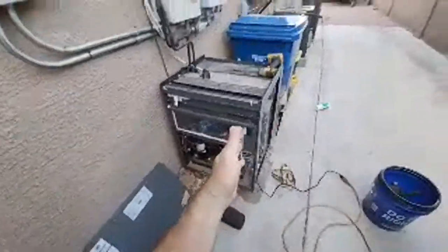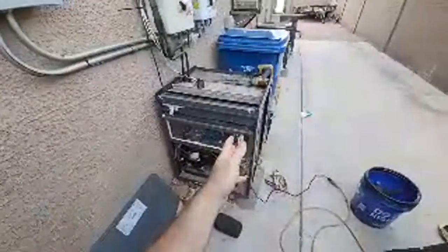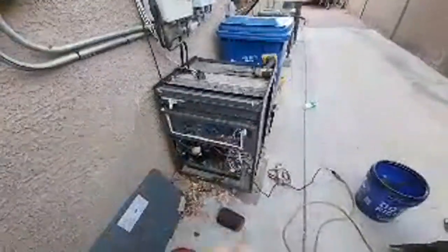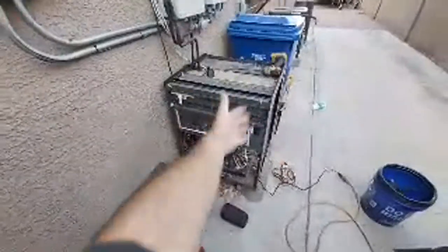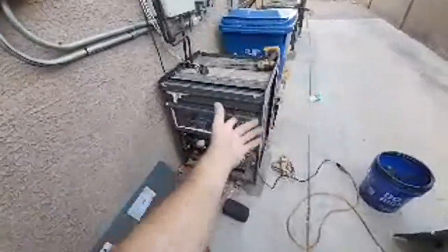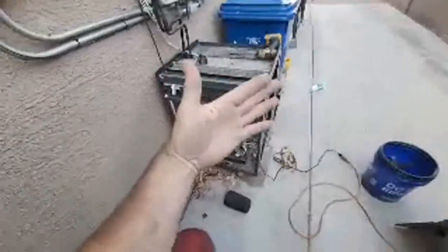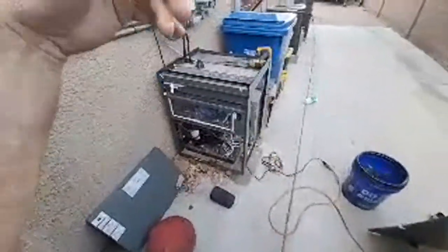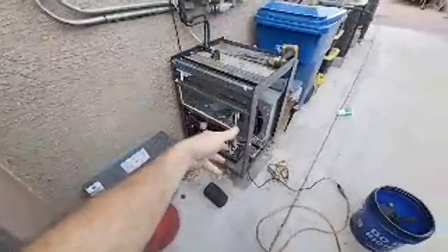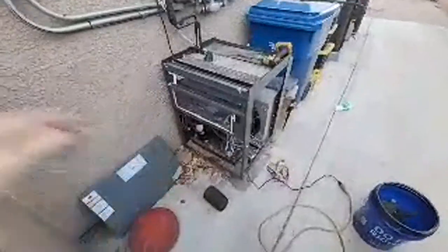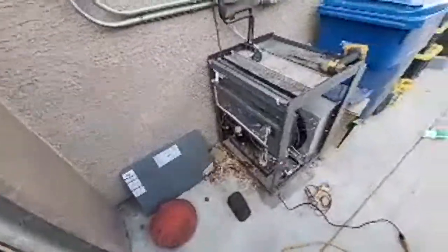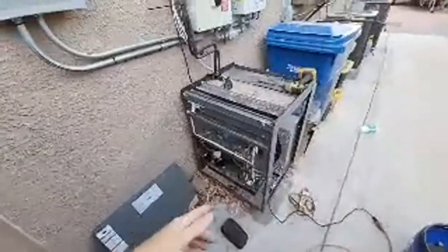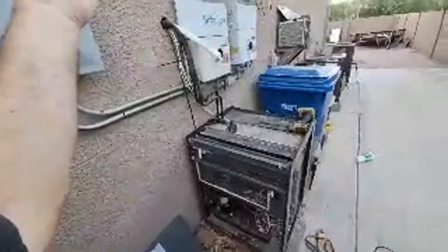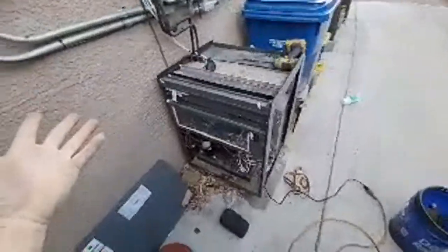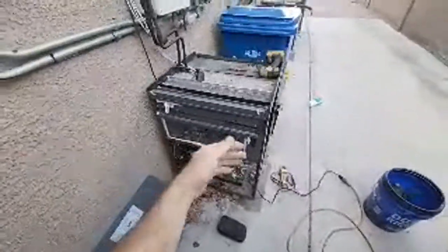So when you send a voltage to the electronic fan motor, an ECM, it starts running on that 2 to 10 volt DC, let's say for example. You get that variable voltage depending on the command, an analog output. The fan turns, it has a tachometer, pulse, pulse, pulse. The pulses at full speed were about 44 hertz on the original fan motor, so the board knows it's going at the right speed, and it adjusts and does its thing. Well, when I got the right high speed on the little fan inside, it was like 300 hertz, way too fast a pulse coming back for speed reference.